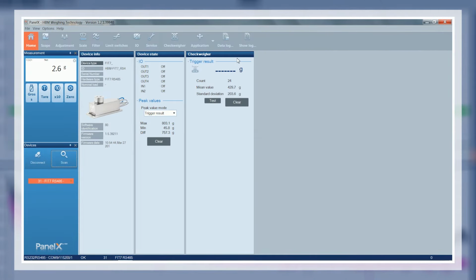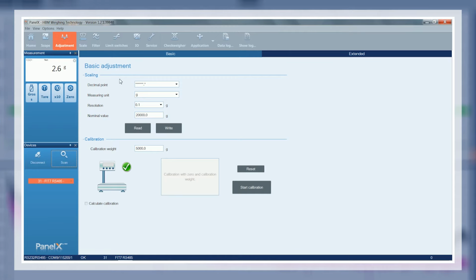In the next step, we will complete a static calibration of the Checkweigher. We open the tab Adjustment and enter the weight value we want to use for calibrating our load conveyor in the field Calibration Weight. In our example, we will enter the calibration weight 5 kilograms.